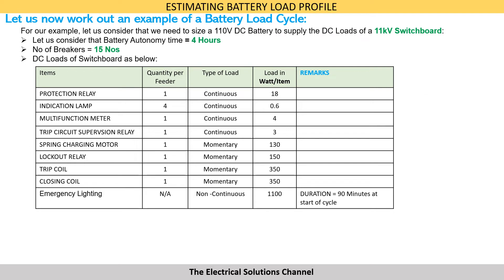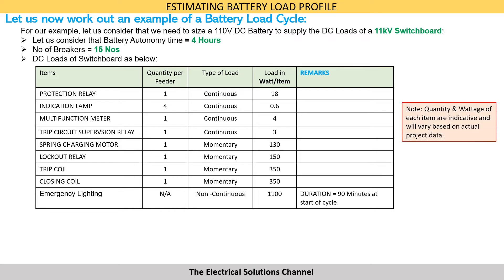The loads include one protection relay, indication lamps, multifunction meter, trip circuit supervision relay, spring charging motor, lockout relay, trip coil, closing coil, and emergency lighting of the switchgear room where the 11 kV switchboard is located. The quantity of these loads in the switchboard is as given in the table, and the type of load — whether continuous, momentary, or non-continuous — is indicated in the table along with the wattage of each load.